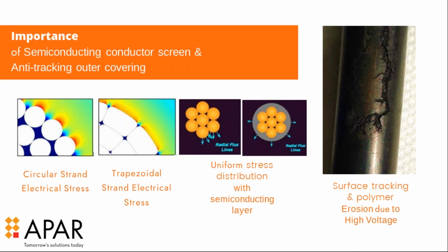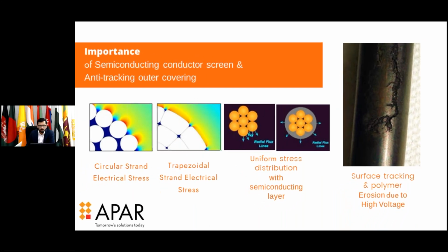Specifically in South Asian countries like India, Pakistan, and others, we all experience a very polluted environment. Though the EN standard says it's up to the utilities to decide whether 11 kV cable should be track resistant or not, we specifically vouch that in these countries the standard should require utilities to ask for track resistant cable, because without it, the cable will fail and you won't get the desired life. This system is being made for 30 to 40 or 50 years, not for a short life. We expect a lifespan of at least 50 years once properly installed on the line.